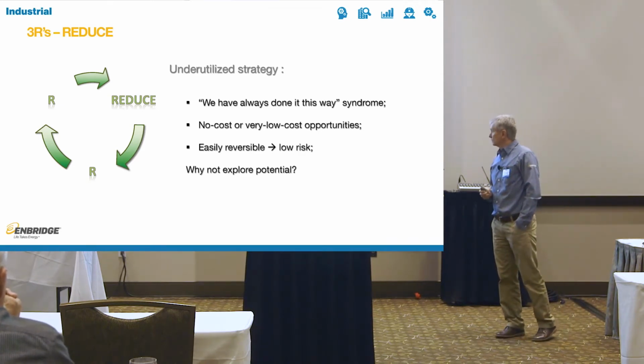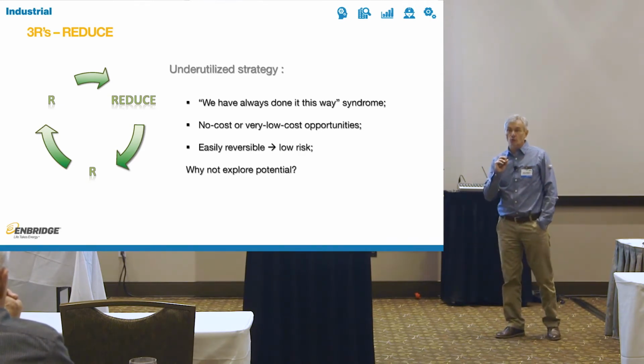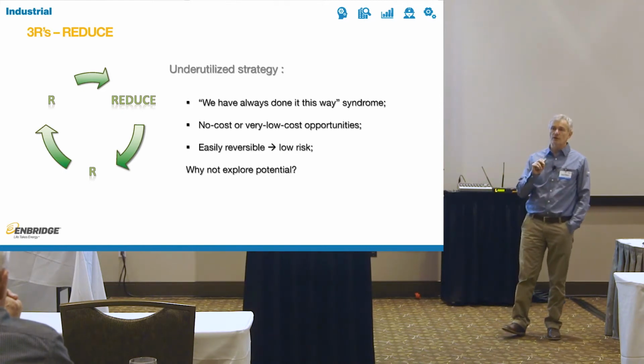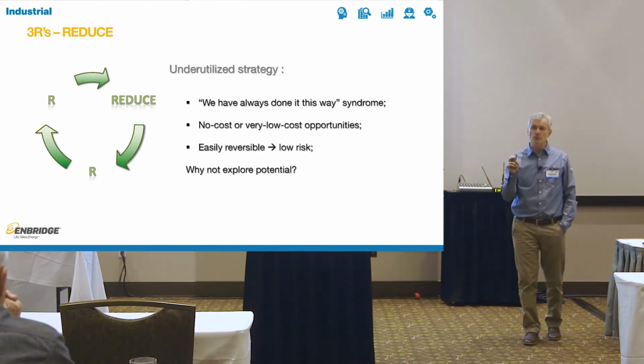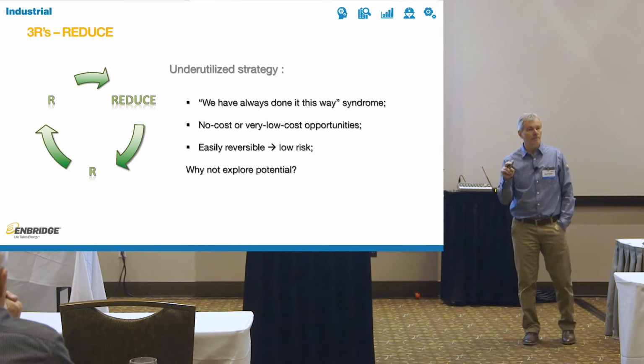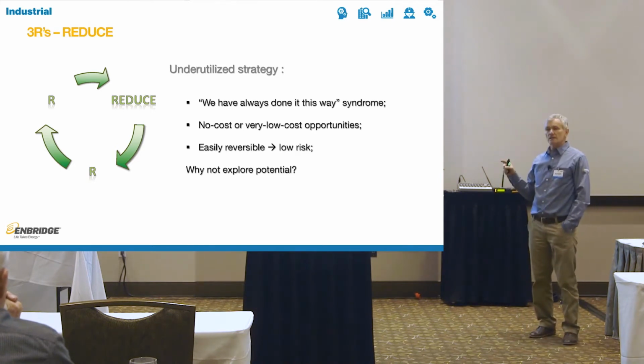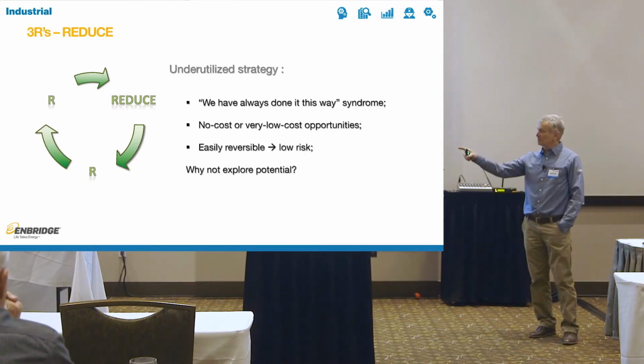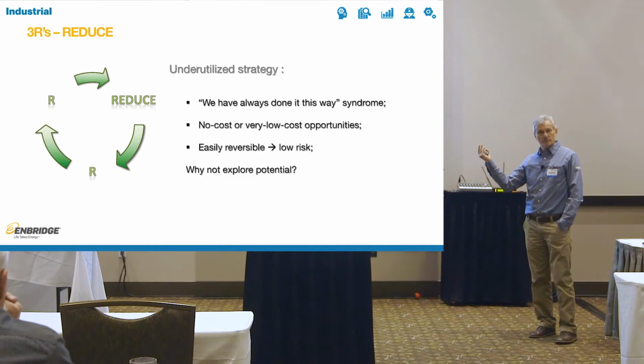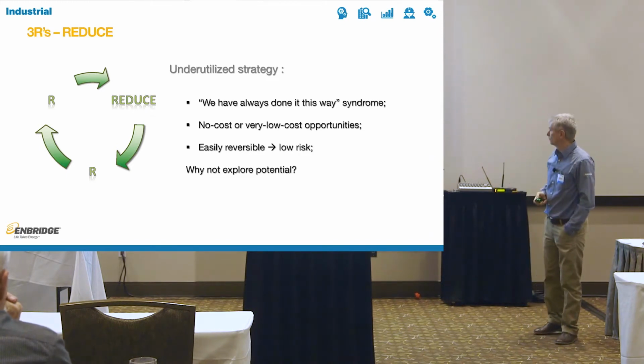The best part of this reducing is that there are always, or almost always, no cost or very low cost opportunities. Changing the set point doesn't cost anything. And it's easily reversible. Even with VFD on the exhaust, as Paul mentioned, if you need to go back up, you turn it back up, you're back where you were. The risk is minimum. So why not explore that potential?